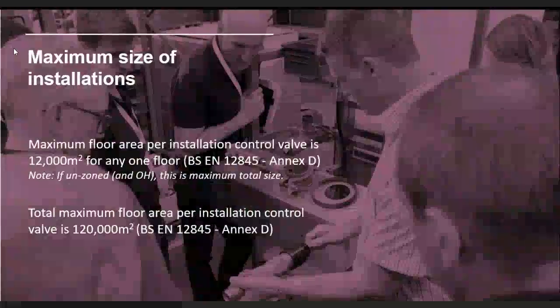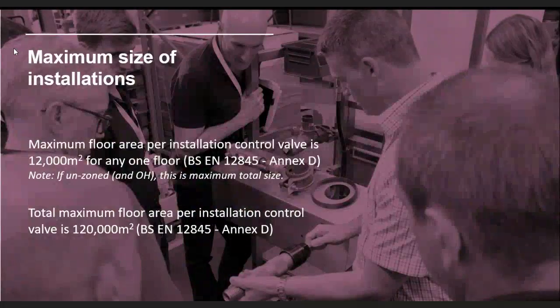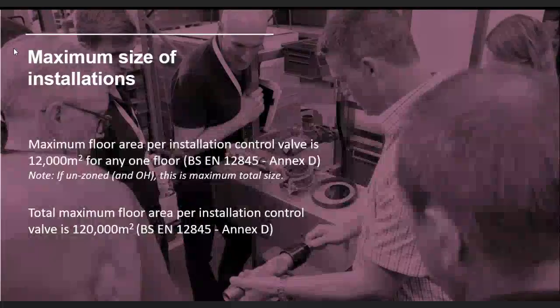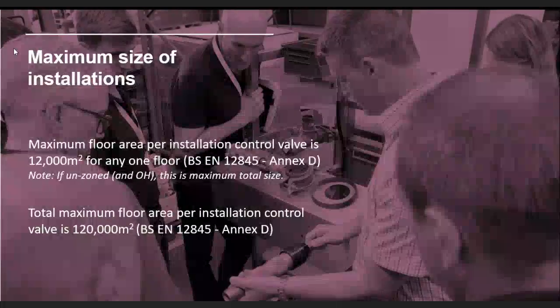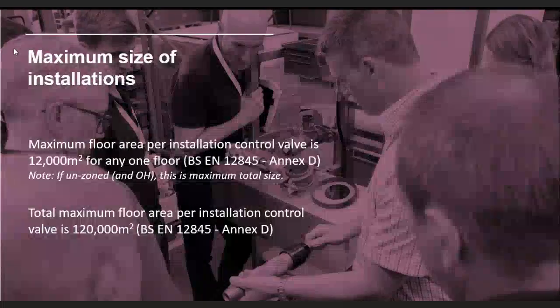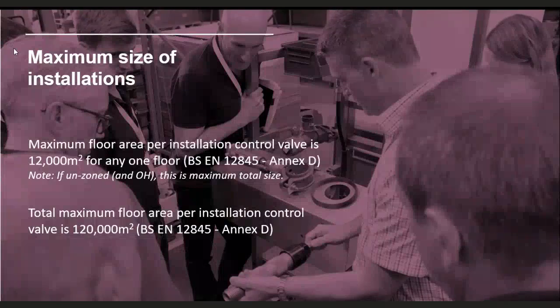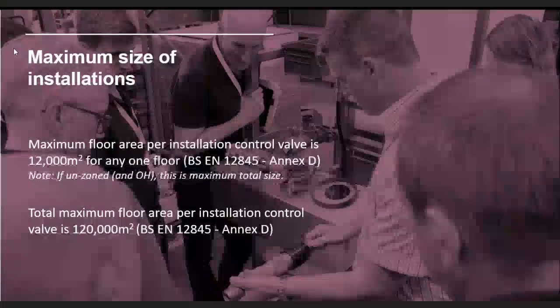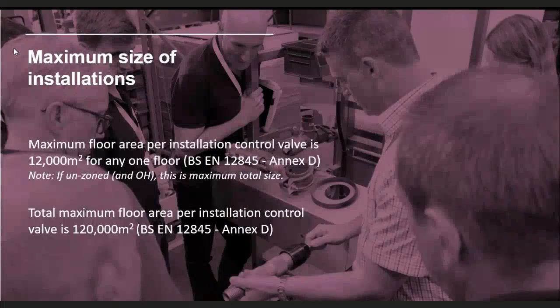Okay, let's look in a bit more detail at the maximum size of installations and zones. First of all, we have the statement here in Annex D. Maximum floor area per installation control valve is 12,000 square meters for any one floor. This is taken from Annex D, which is about zoned systems. Maximum floor area per installation control valve is 120,000 square meters. Just a note there: if it's unzoned and it's ordinary hazard, then this is the maximum total size.